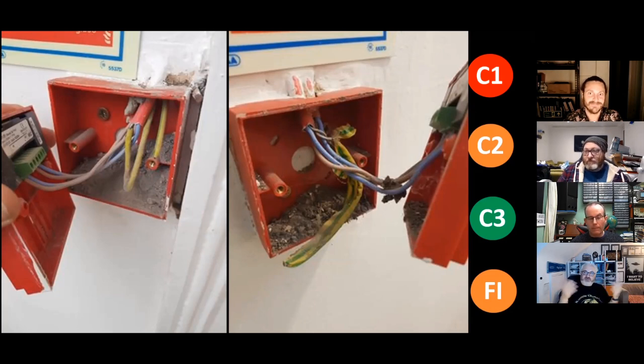Use a pan head or a mushroom head, whatever you want to call it. Then you've got a flat cross-sectional area as much as you can, even if you're using a penny washer. Use a penny washer and a countersunk screw, you're using the wrong combination. Don't do it. See if the manufacturer says anything about that. They probably haven't thought about it. This is old school engineering that I was taught in my second week of my apprenticeship, when I started using countersunk screws and was made to spend 2 days screwing things into walls. The other issue with those screws, not so much on the new ones, but on the old ones, particularly the slot head, is that the edge of it used to be really sharp.